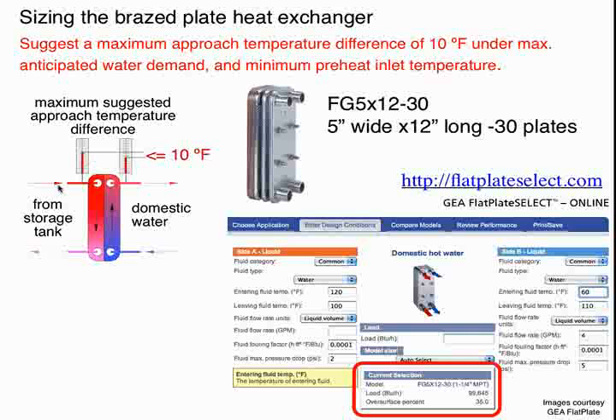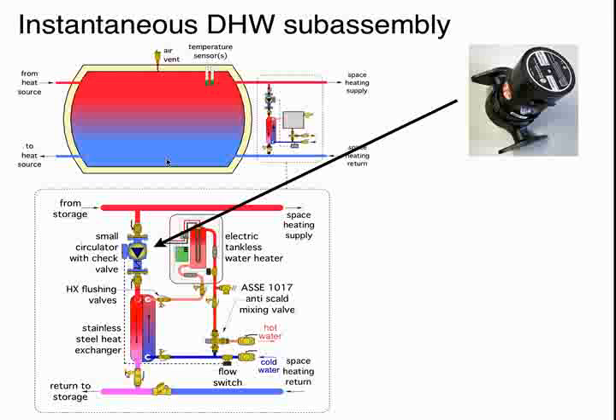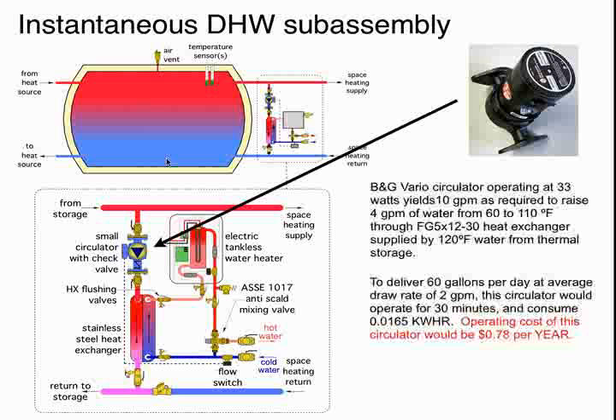You can size up a brazed plate heat exchanger pretty quickly with some of the online software that's out there. When you do that, try not to have more than a 10-degree difference between the incoming storage tank temperature and the leaving domestic water temperature. The larger the heat exchanger is, the smaller this approach temperature difference will get. Within reason, I would say 5 to 10 degrees Fahrenheit will work good there.